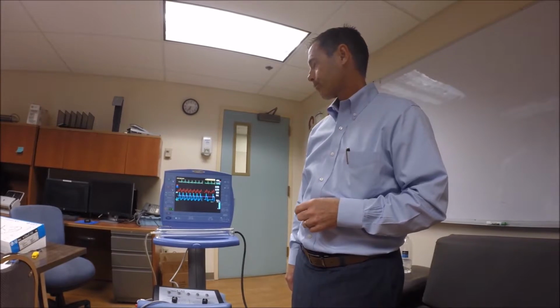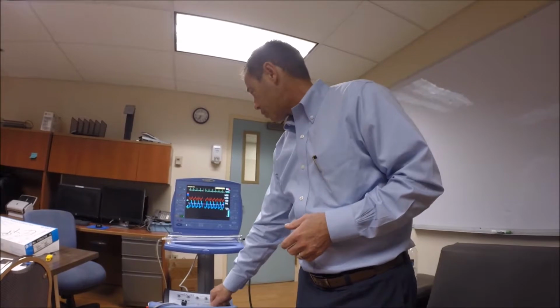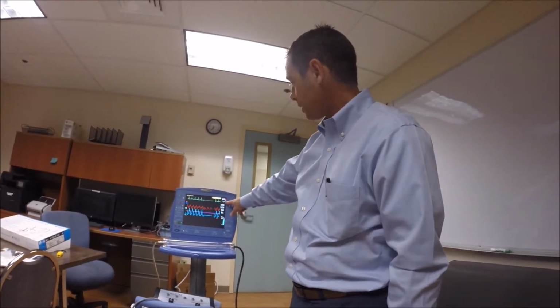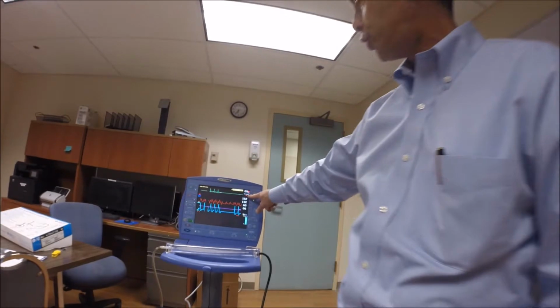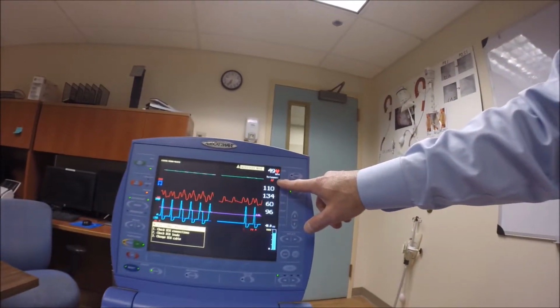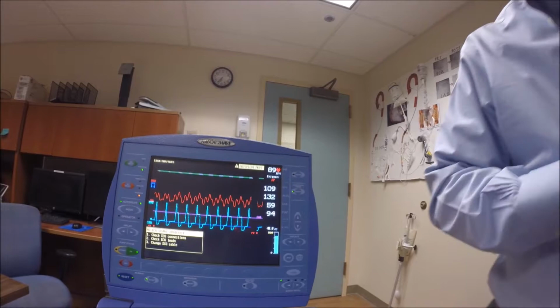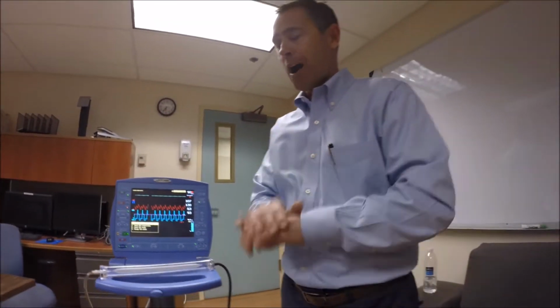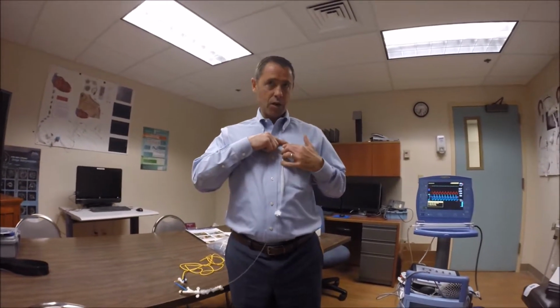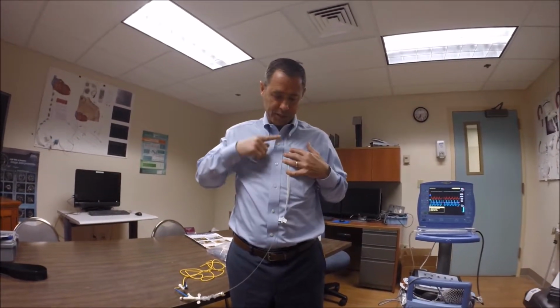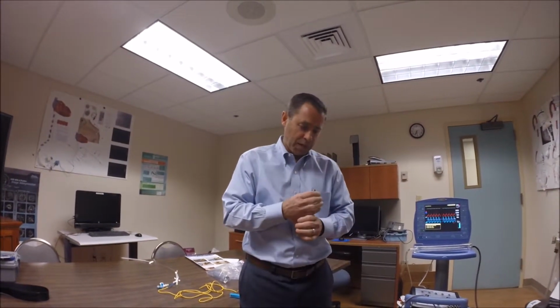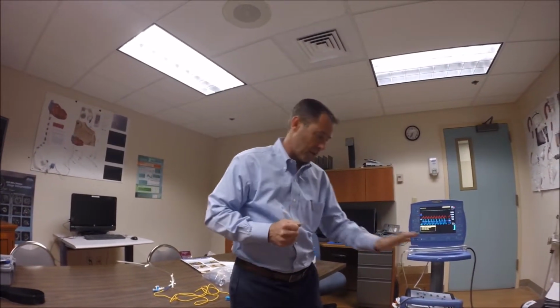All right. Let's talk about what happens during a code. If my patient were to code and it goes asystole, my triggering mechanism instantly jumps to AP, which is arterial pressure. Arterial pressure is just that. It's chest compressions. So on my catheter, my sensor sits right here next to my heart. And as I'm compressing down, it hits the sensor, which triggers at the speed of light. And so regardless of how erratic my compressions are, I'm still getting proper inflation and deflation with the pump on.